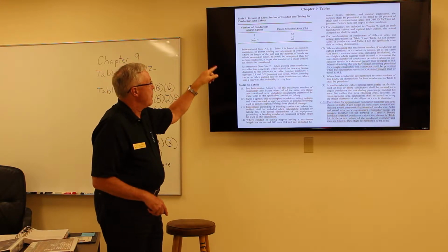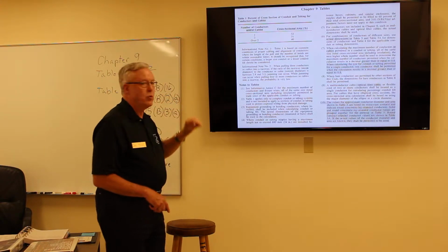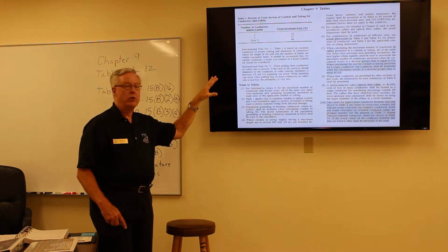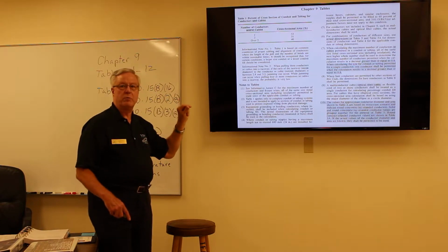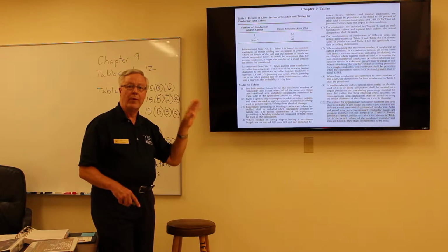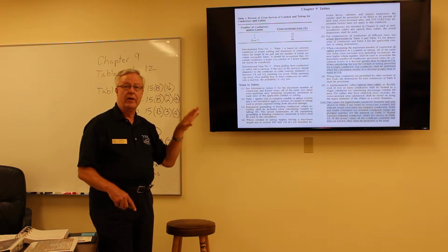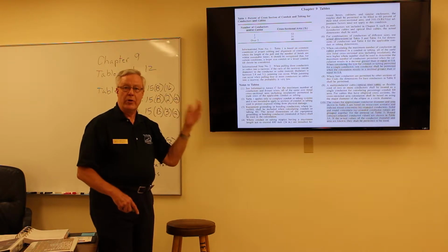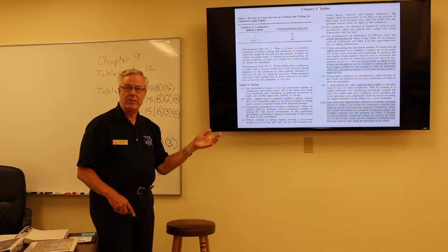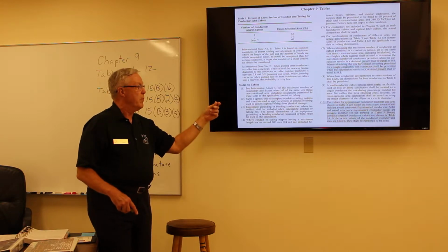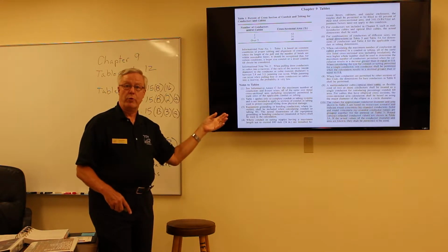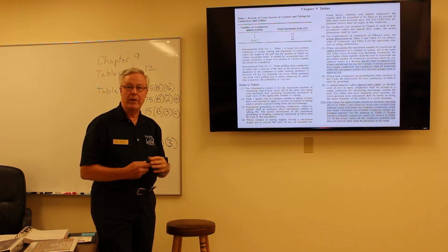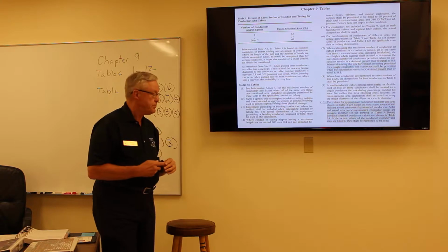Table 1 talks about the number of the conductors, but there's 2 informational notes. Since the minimum standard is what the National Electrical Code is written on, the informational notes basically tell you that depending on the application, when sizing the correct conductors inside the conduit, you have to take into consideration the length of the run and the amount of bends in it. Since this is the minimum and based on tables 1 through 12, you may upsize it depending on the application.